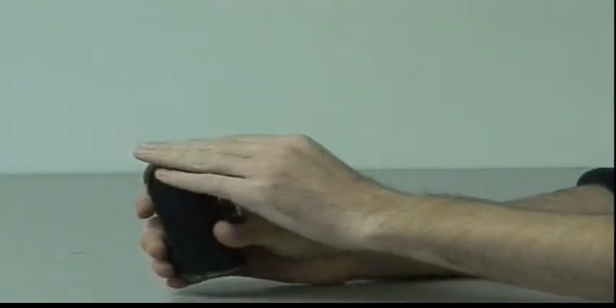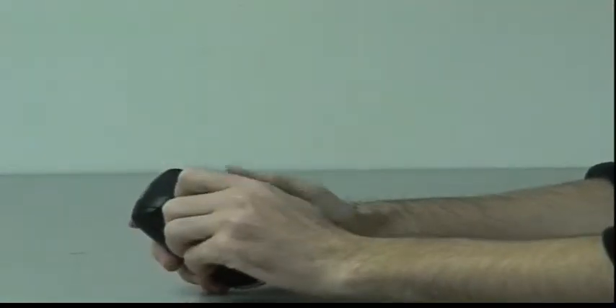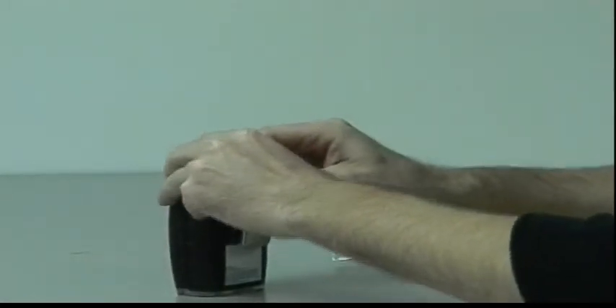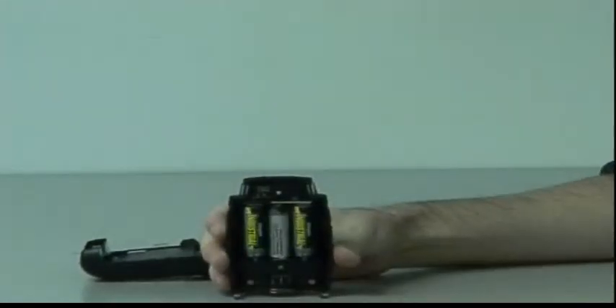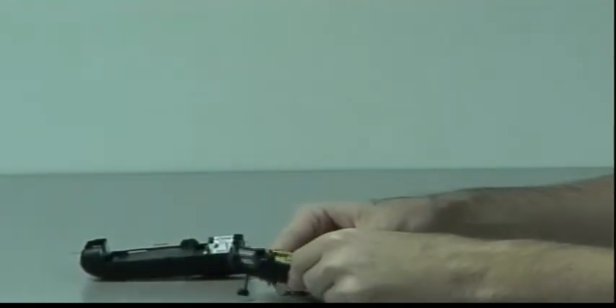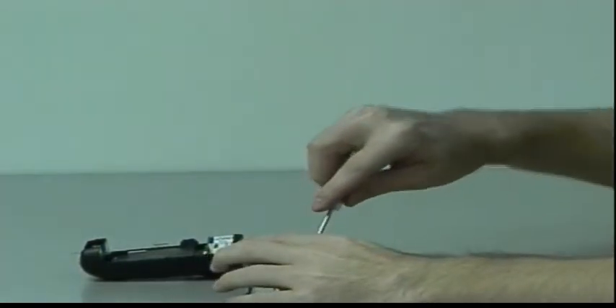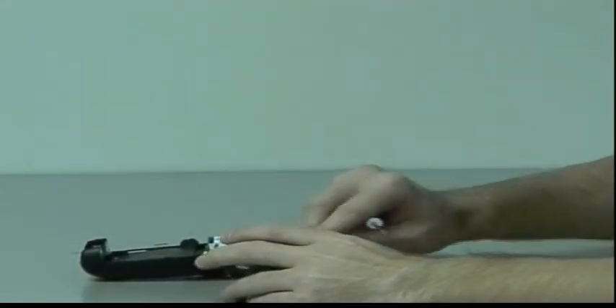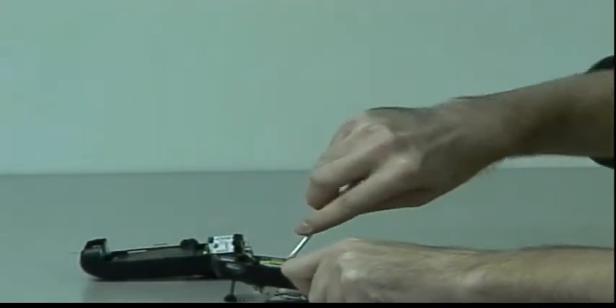To remove the battery, first loosen the top center screw on the back of the instrument. Then gently pry the two clasps at the top of the instrument open, while simultaneously pulling back on the back cover plate away from the main instrument housing. Since the battery pack is housed in the back cover plate, this will automatically disconnect power from the instrument.